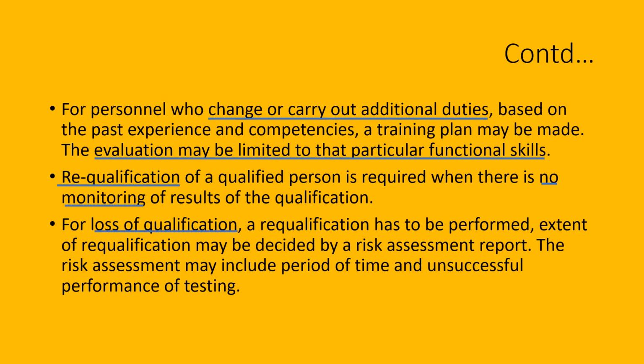For loss of qualification, a requalification has to be performed. The extent of requalification may be decided by a risk assessment report. The risk assessment may include period of time and unsuccessful performance of testing. A risk assessment should decide the extent of requalification for loss of qualification. Loss of qualification means being unable to perform the tests efficiently. It could be based on the period of time and unsuccessful performance of testing.